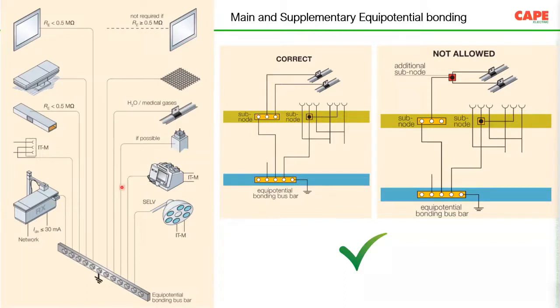The lights, the monitoring system, the medical gas, and the other extraneous conductive parts such as the wash basin, all the metal parts in that location are connected to a common bus bar, and this is called supplementary equipotential bonding. One of the first and foremost electrical safety requirements in a medical location is to have supplementary equipotential bonding. In the picture, I am just showing how to make it, but there are several rules to be followed.